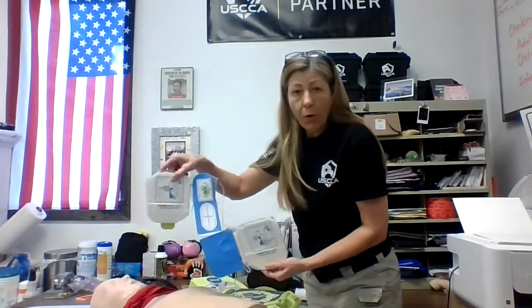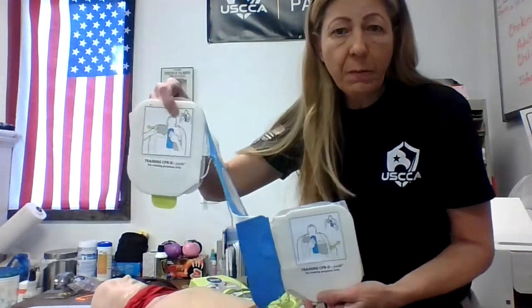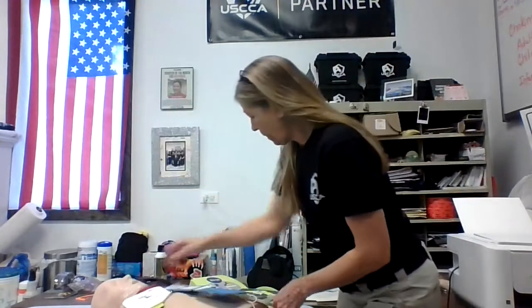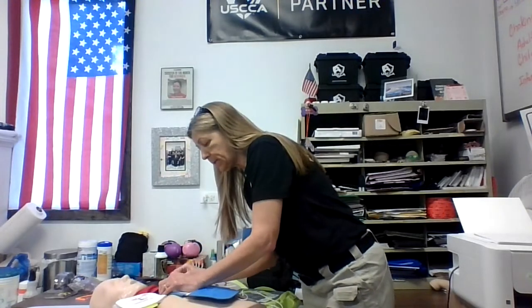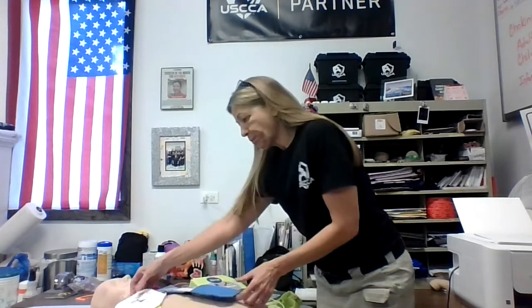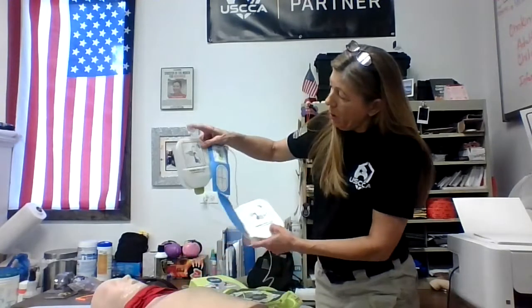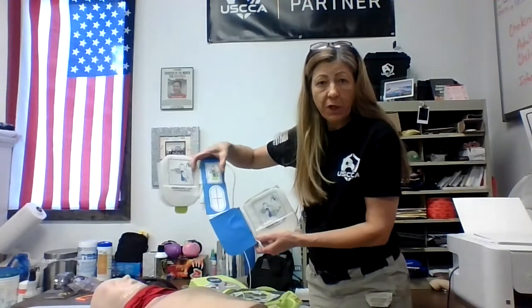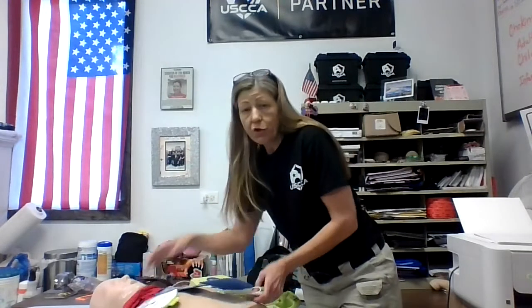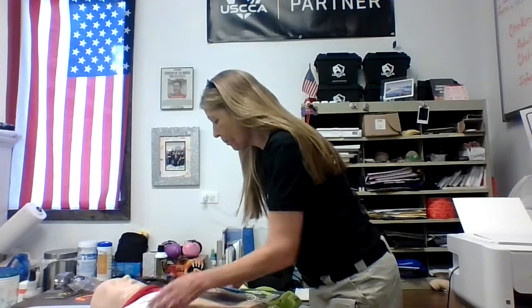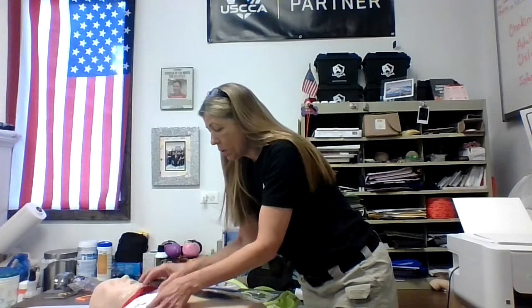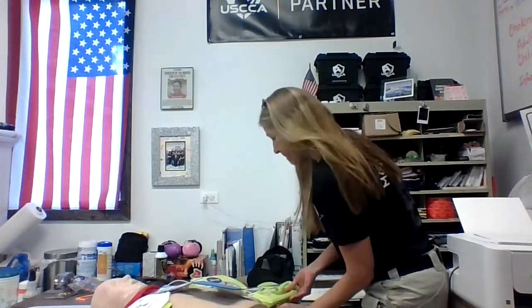So I would pull the adhesives off the back. The pictures are on all the pads as to where the placement is going to be. In this particular machine, what's really nice about this set of pads is that this blue piece keeps the two pads from touching, because like your jumper cables, you wouldn't want them to touch. You line up the cross on the nipple line and the nose and peel the backing off, exposing the adhesive right onto their chest.